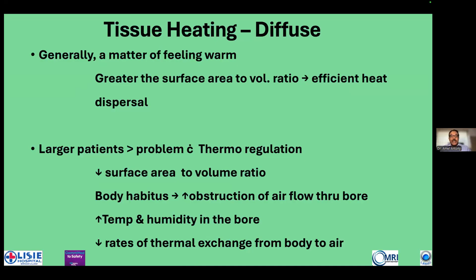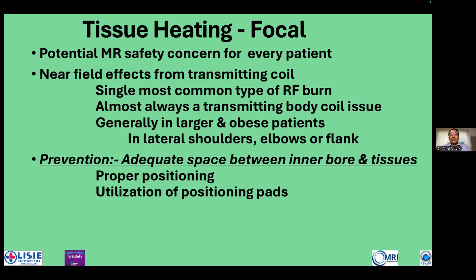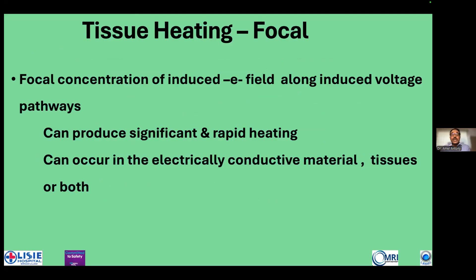Now, prevention of this focal heating is by adequate spacing between inner bore and tissues. That means the body of the patient should not be in contact with the inner bore of the magnet, for which every vendor has provided adequate pads, so that should be used lavishly in proper positioning. And we know that there is focal concentration of induced electrical fields along induced voltage pathways, especially when body parts come in contact with each other. So that can produce significant and rapid heating.